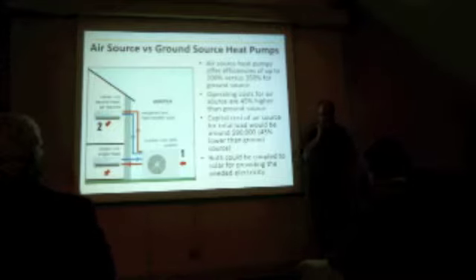So if you do the same exercise for air source and accept the lower efficiencies of operation, it could be done. You could get your heat load from air source heat pumps. The capital cost is less because you're not drilling into the ground. So it would be about $90,000 to buy and install the air source heat pumps. But for every unit of heat, they're about 45% more expensive than ground source heat pumps because they're less efficient. They need more electricity bought. And the part Melissa will talk about is that these can both be powered off of a solar array if the church was to move in that direction.